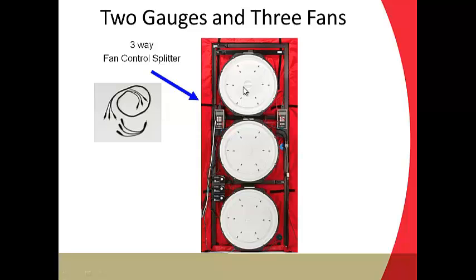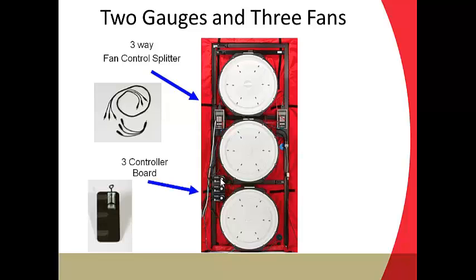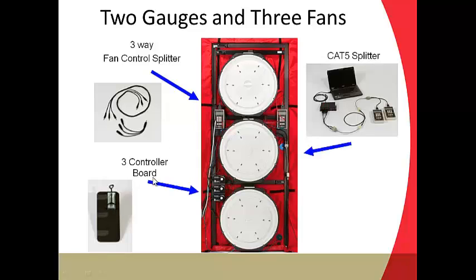And if we're getting low fan pressure at the fans, then we'll cap one fan and shut off the controller to it. So rather than using rings, we just start shutting fans down. It's a lot easier to keep track of than which fan did I put that ring on, and keeping track of those kinds of things. So the 3 controller board, we talked about that.